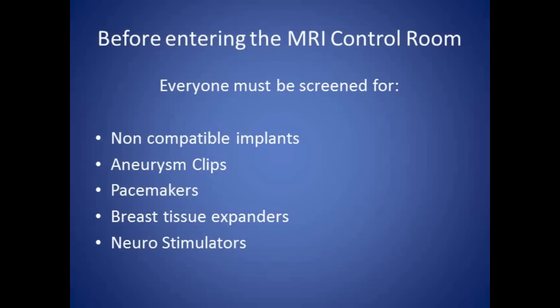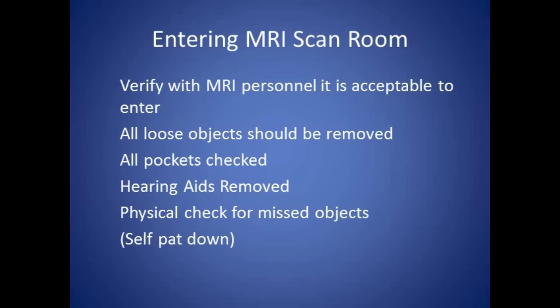Before entering the MRI scan room, verify with MRI personnel that it is acceptable to enter. All loose objects should be removed, all pockets checked, hearing aids removed, and a physical check done for any missed objects on your person. Loose objects that are ferromagnetic will be pulled from your person. If they are attached to you and large enough, they will pull you with them.